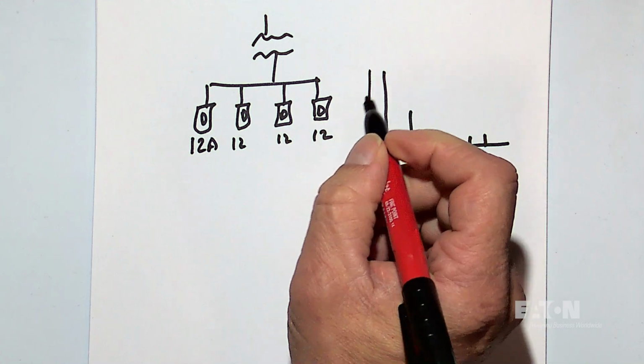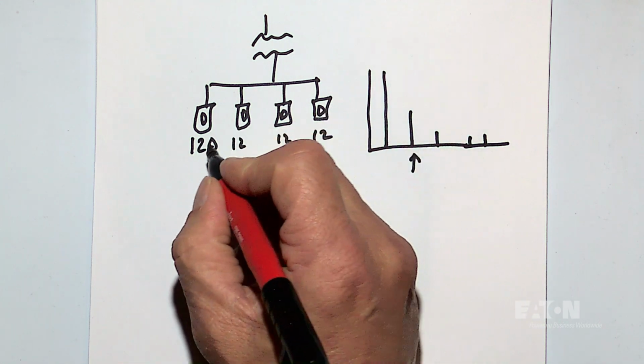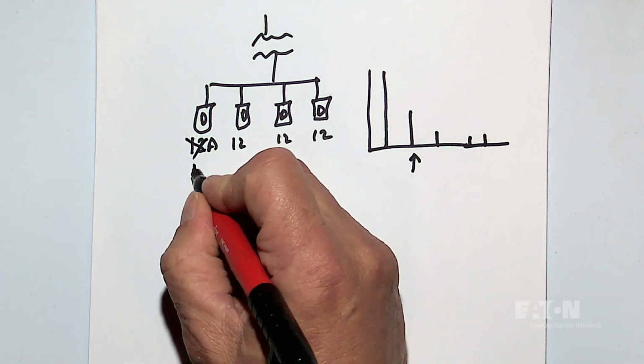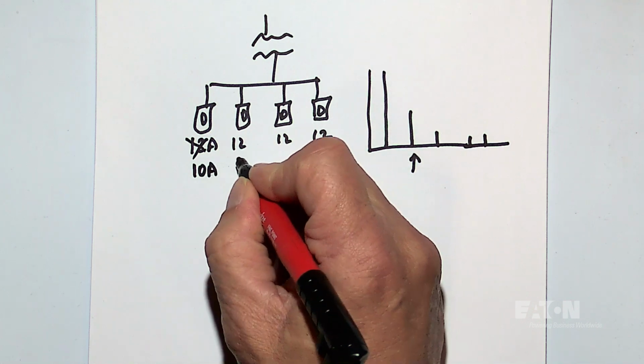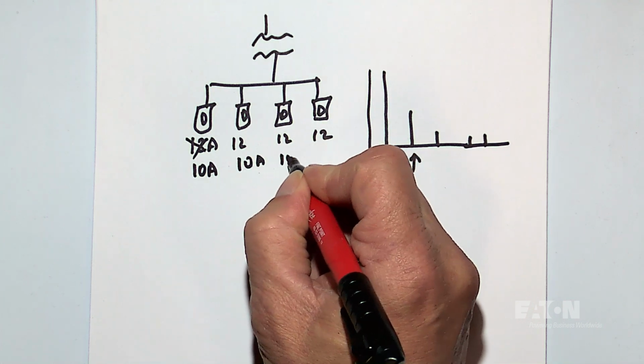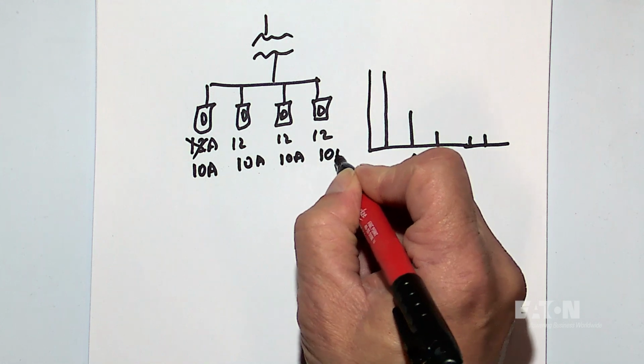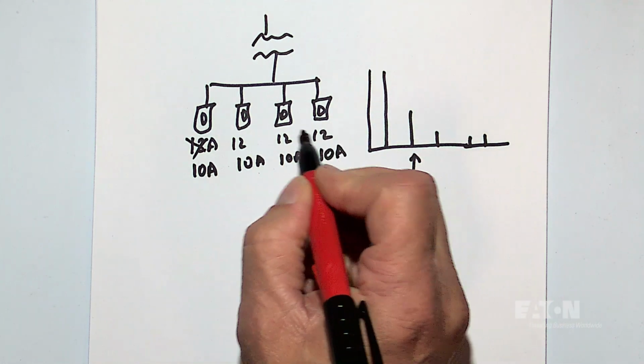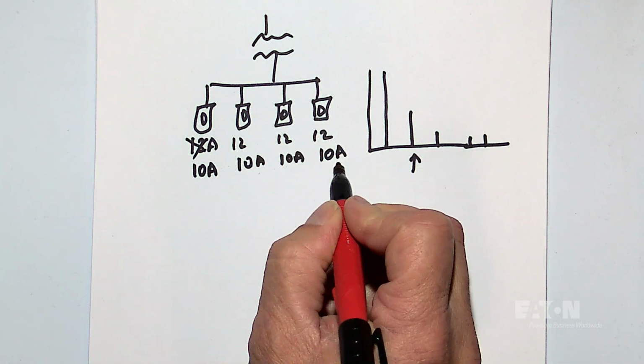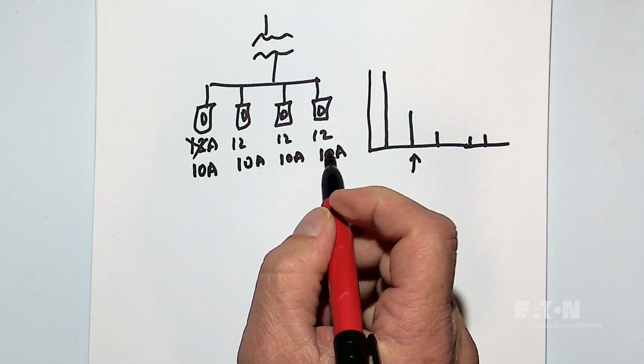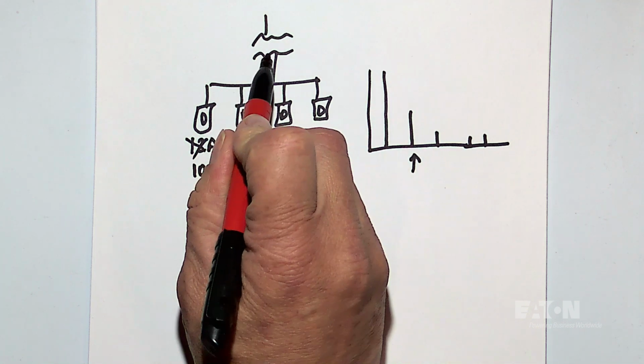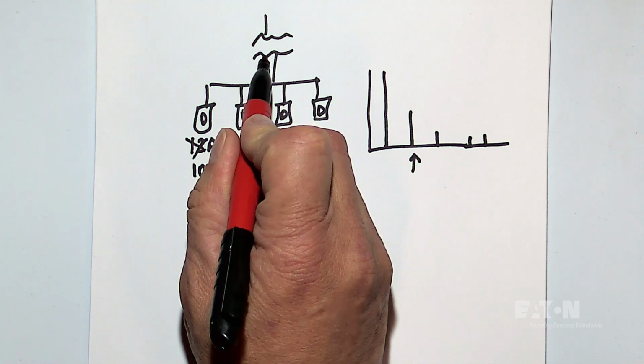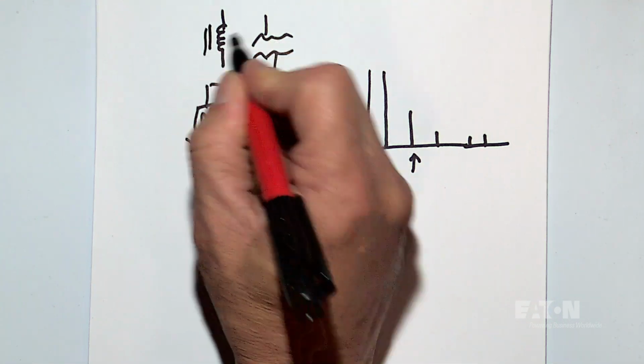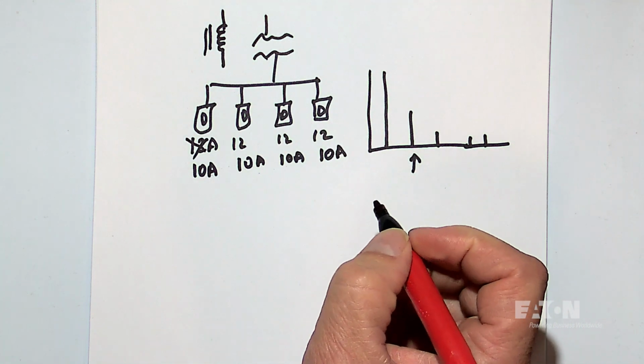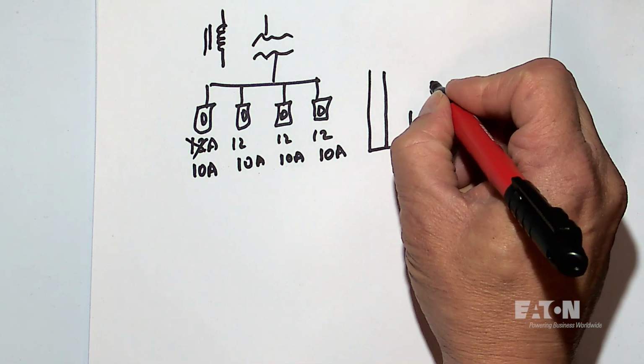But in fact, if we turn all 4 drives on, it's really more like maybe 10 amps, 10 amps, 10 amps, and 10 amps. So why the difference? Why is it different when we put 4 drives on versus having just one drive by itself? And the reason is because of this guy, the transformer. This transformer ends up looking like a line reactor. And what does a line reactor do? We've talked about it many times, but it basically constricts the current.